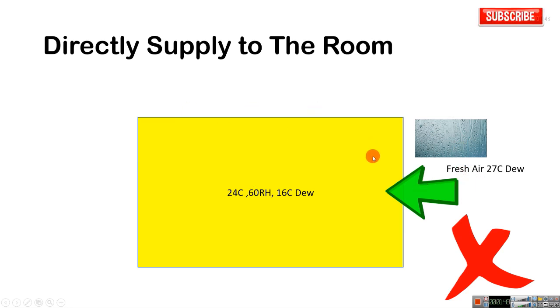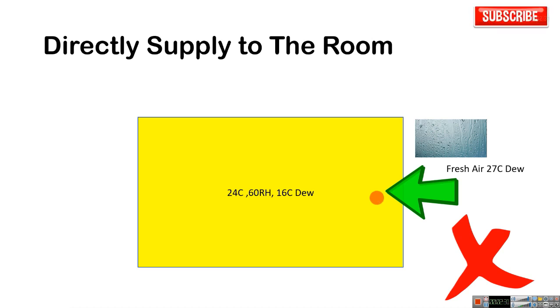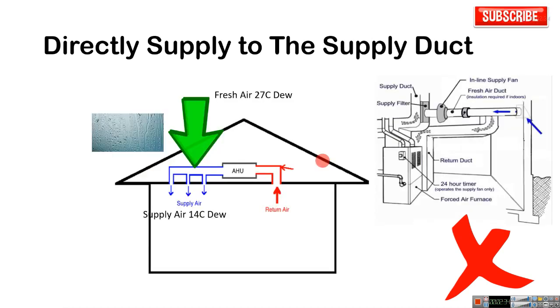You can see the fresh air is directly supplied to the room. The room temperature is 24°C, RH 60%, and dew point 16°C. Our fresh air dew point is 27°C. If we supply our fresh air directly to the room, the area near the fresh air diffuser will condensate. This means the fresh air supply point will definitely cause condensation, so this is a wrong connection type.